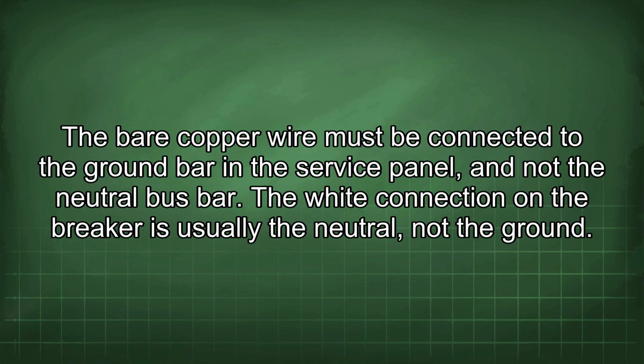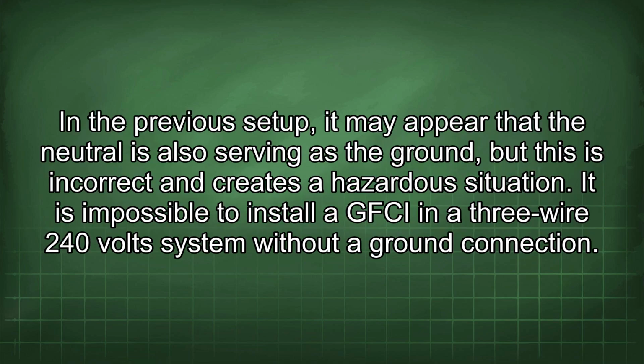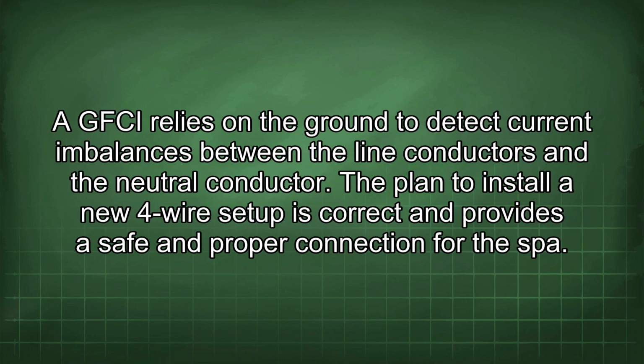bar. The white connection on the breaker is usually the neutral, not the ground. In the previous setup, it may appear that the neutral is also serving as the ground, but this is incorrect and creates a hazardous situation. It is impossible to install a GFCI in a 3-wire 240-volt system without a ground connection. A GFCI relies on the ground to detect current imbalances between the line conductors and the neutral conductor.